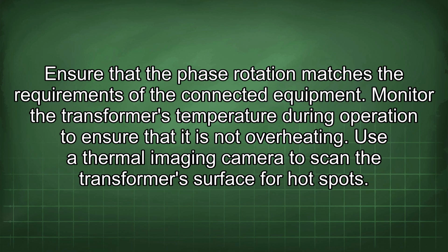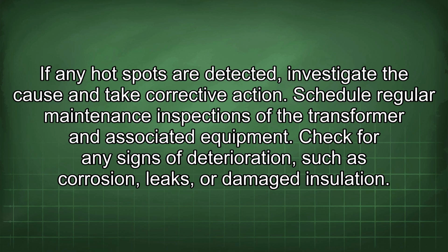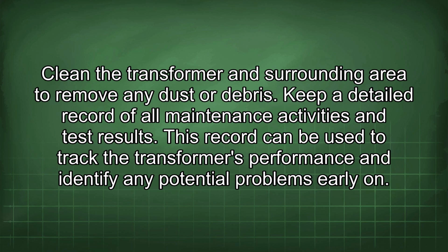Monitor the transformer's temperature during operation to ensure that it is not overheating. Use a thermal imaging camera to scan the transformer's surface for hot spots. If any hot spots are detected, investigate the cause and take corrective action. Schedule regular maintenance inspections of the transformer and associated equipment. Check for any signs of deterioration, such as corrosion, leaks, or damaged insulation. Clean the transformer and surrounding area to remove any dust or debris.